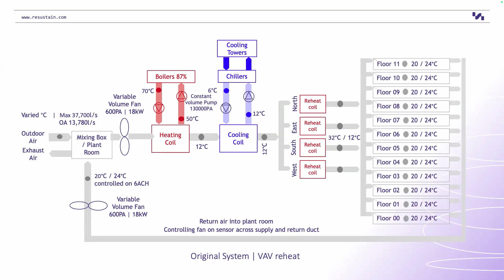What they did was they decommissioned the cooling part of the VAV system and fitted VRFs into each of the tenant spaces. A very typical retrofit, I would say, in the UK, is VRFs being retrofitted into tenant spaces. It's great, but also very typical. But what they didn't do is then look at the changes that needed to happen within the air handling unit in order to support those VRFs and make sure that all the spaces were comfortable.